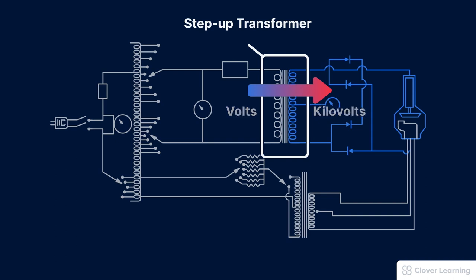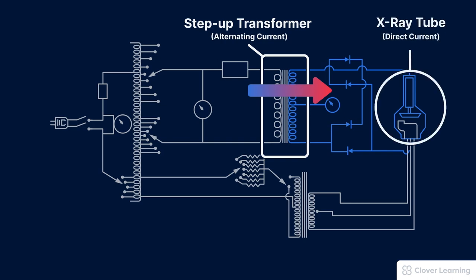Transformers work only when using alternating current, but the x-ray tube must operate using only direct current or DC current. Imagine what would happen if the current was alternating in the x-ray tube. Electrons are supposed to flow from cathode to anode, but an AC current would cause the electrons to flow in both directions, and obviously that would be a problem.